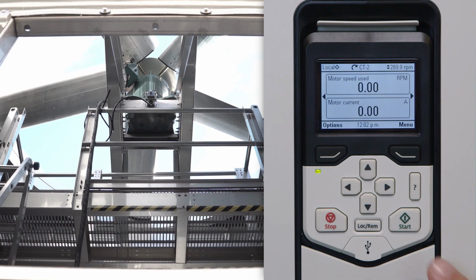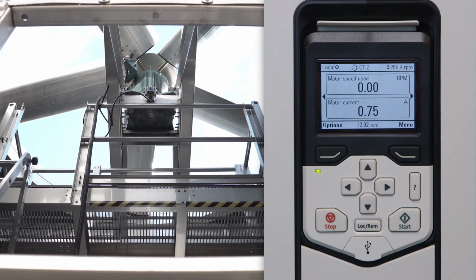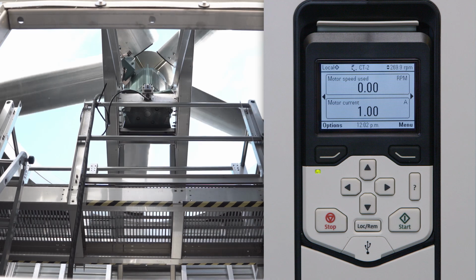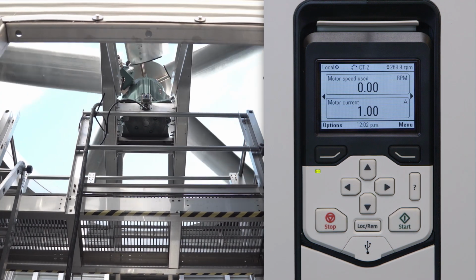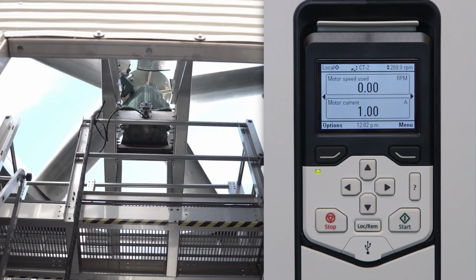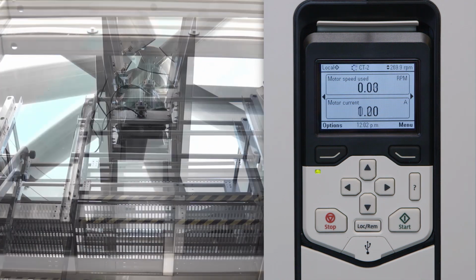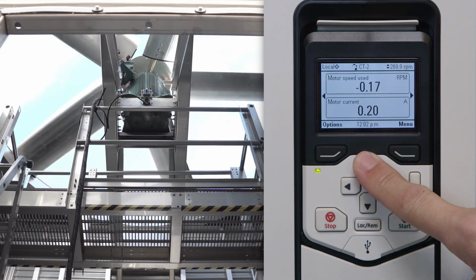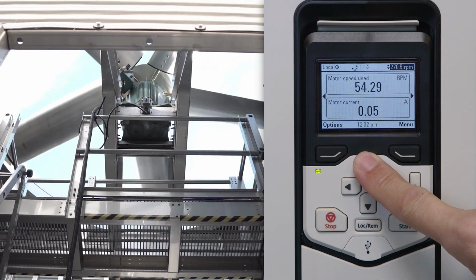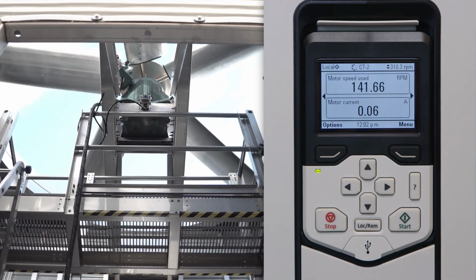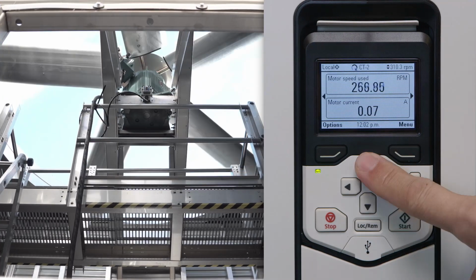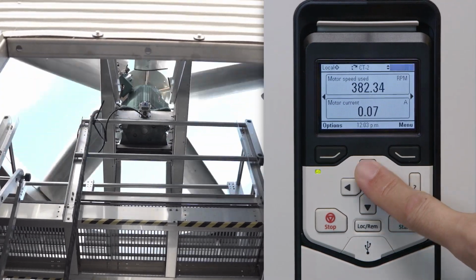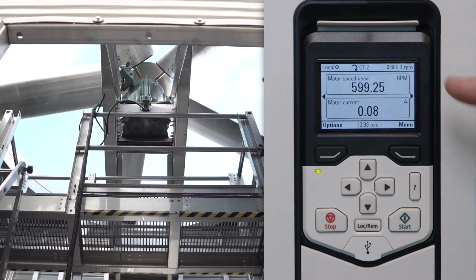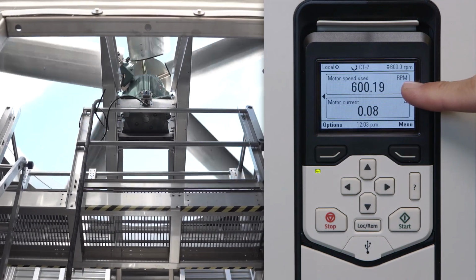Press the Start button. The motor should auto-ramp. The default value is 15 seconds but can be configured for longer or shorter ramp-up. Using the up arrow, increase the fan speed to 100%. Check that the amps at full speed do not exceed the nameplate amps. Now press Stop.